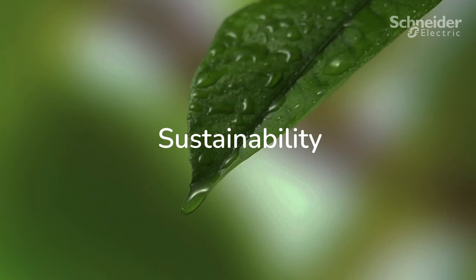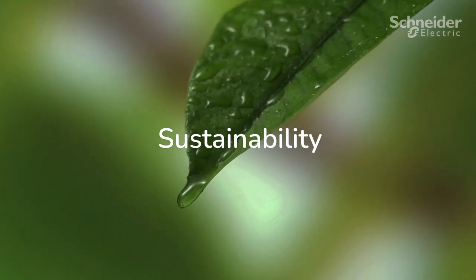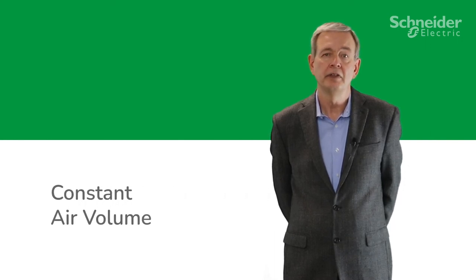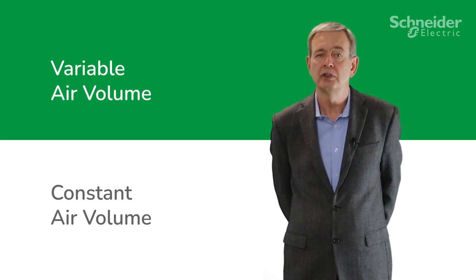The Eurotherm digital fume hood VAV kit helps to make laboratory fume hoods more sustainable. Within a laboratory, a fume hood can be the device with the most significant impact in terms of energy demand. The initial expenditure of converting a constant air volume, or CAV, ventilation system to a VAV system is an investment that typically has a short payback period while providing operational, environmental, and compliance benefits.